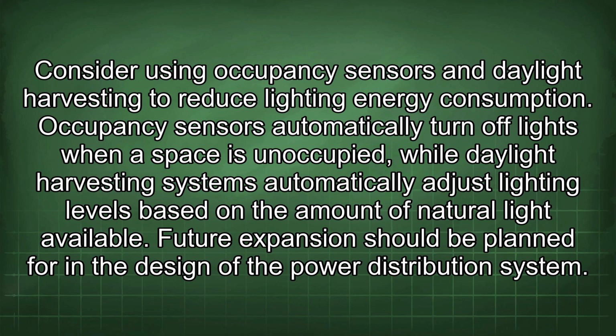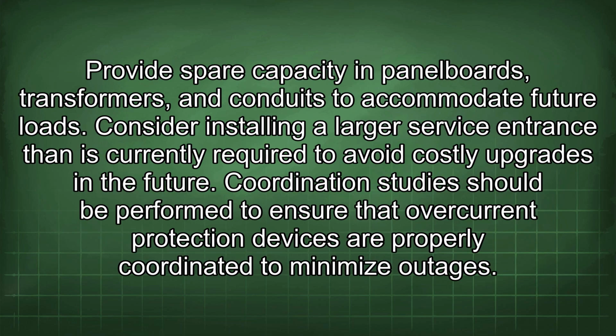Future expansion should be planned for in the design of the power distribution system. Provide spare capacity in panel boards, transformers, and conduits to accommodate future loads. Consider installing a larger service entrance than is currently required to avoid costly upgrades in the future.